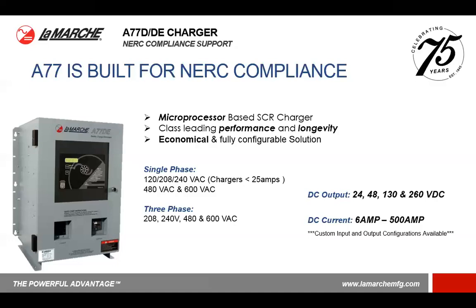And since this charger complies with the industrial battery charger requirements, the filtering level in this charger is offered in two levels: either a battery eliminator, or level 2 if you reference IEEE P2405, or a filtered battery charger, or level 1 if you reference IEEE P2405, in regards to filtering in the output. For level 2, it drops the output of the lower DC voltages to less than 30 millivolts, or for the higher ones to less than 100 millivolts, with or without a battery connected.